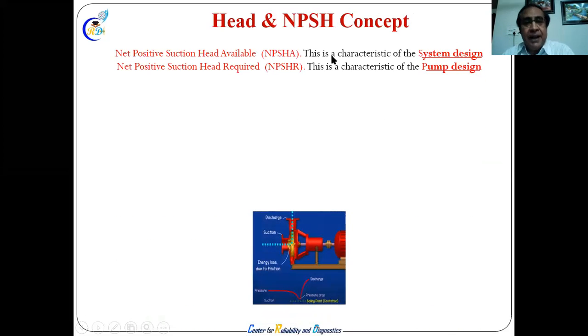Okay, so in a nutshell, this is a characteristic of system design. When designing the system, the availability of the machine should be as required. And the availability requirement is a pump design matter. In system design, the site condition we are considering, for which the pump is used, that is availability. Where our pressure is coming from, where we take the water from, drum, liquid, cooling water, tanks, and what the height is, all the calculation has to be done. So it is needed during the entire piping system design. I require that the pump manufacturer takes care at the design stage, engineering stage. Okay, so that is the thing.